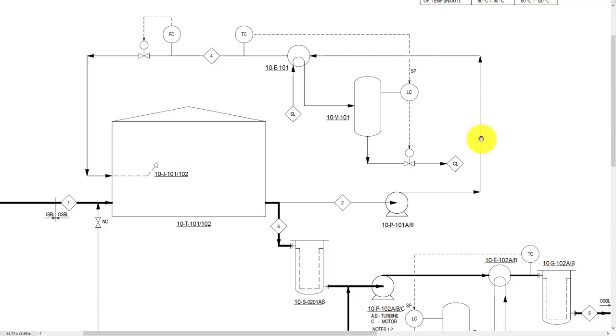Now look at this loop. This is a circulation loop. Fuel oil from the tank is supplied to the pump, which is passed through the heat exchanger and returned to the tank. You have to maintain the temperature of the fuel oil, otherwise it will get thick and choke the line and also settle in the tank.